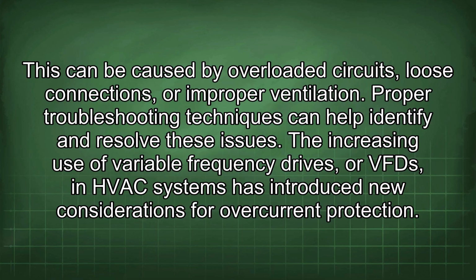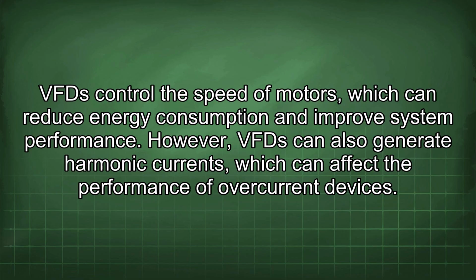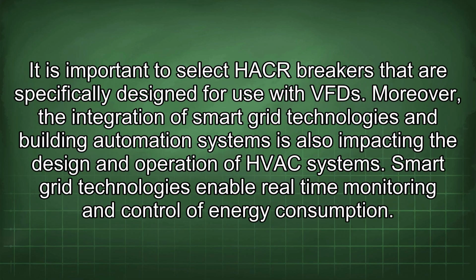The increasing use of variable frequency drives, or VFDs, in HVAC systems has introduced new considerations for overcurrent protection. VFDs control the speed of motors, which can reduce energy consumption and improve system performance. However, VFDs can also generate harmonic currents which can affect the performance of overcurrent devices. It is important to select HACR breakers that are specifically designed for use with VFDs.